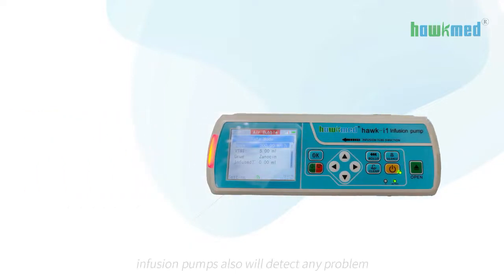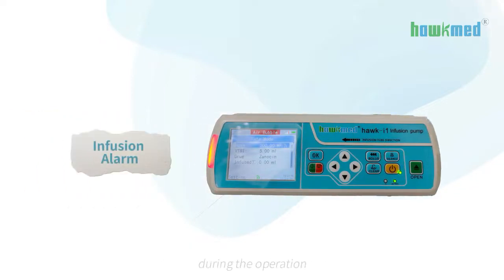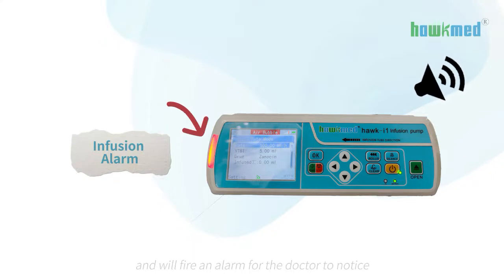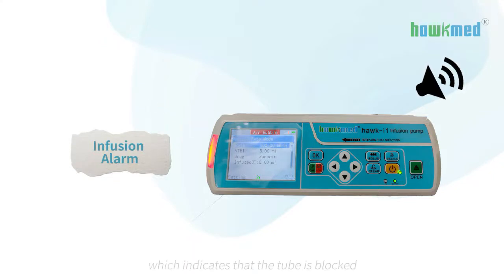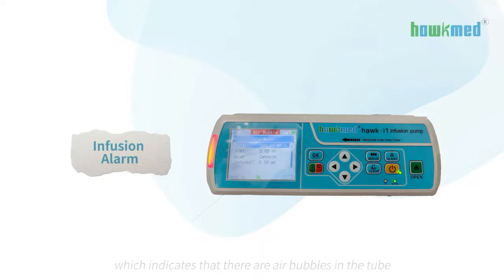Infusion pumps also will detect any problem during the operation and will fire an alarm for the doctor to notice, like the occlusion alarm which indicates that the tube is blocked, and the air in line alarm which indicates that there are air bubbles in the tube.